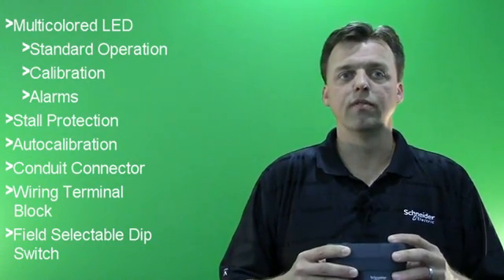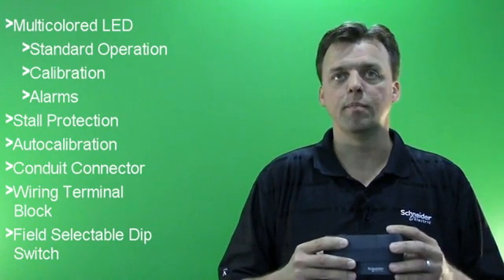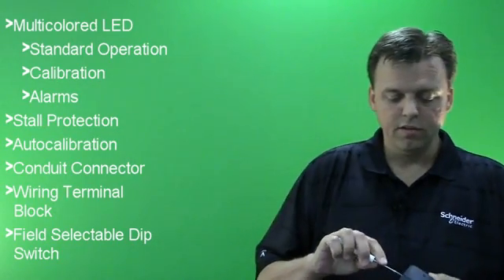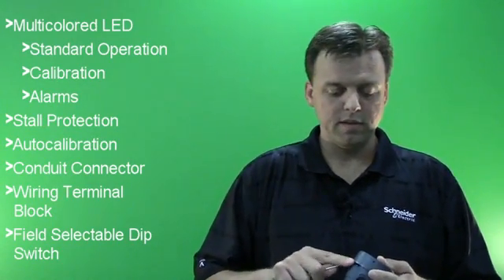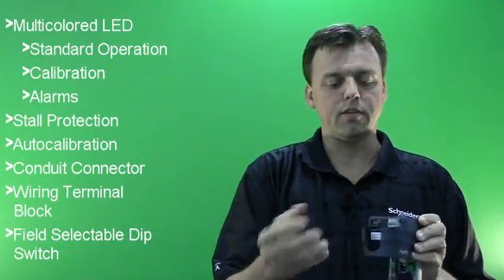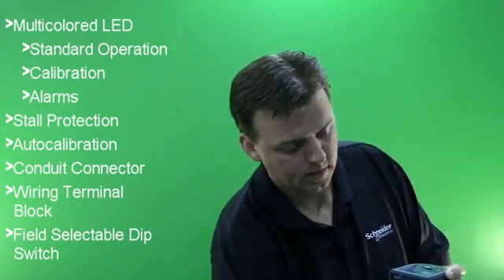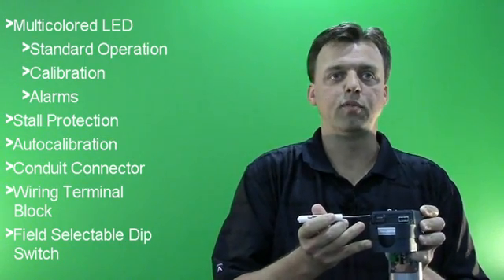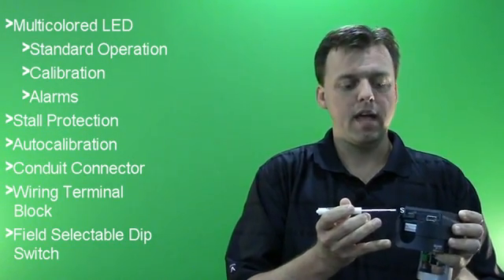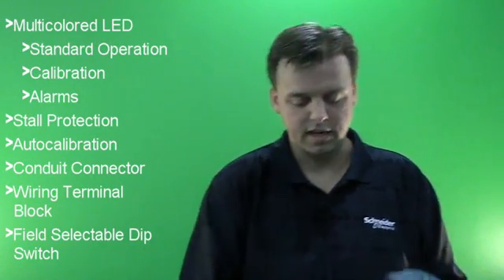The auto-calibration feature delivers precise control by scaling the input signal to match the exact travel of the valve stem. Under the wiring compartment, we have an easy-to-remove conduit connector as well as a wiring terminal block. We also have a field-selectable DIP switch for 0-10, 2-10, and 4-20 milliamp input signals, as well as direct acting and reverse acting.